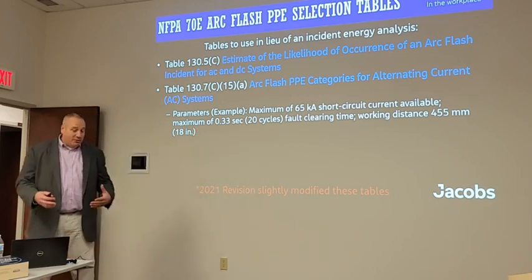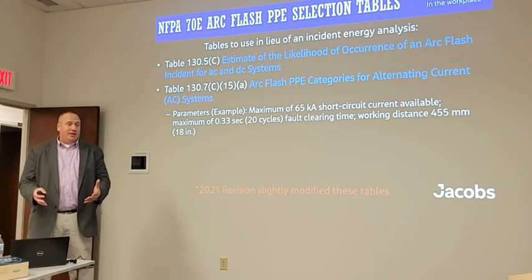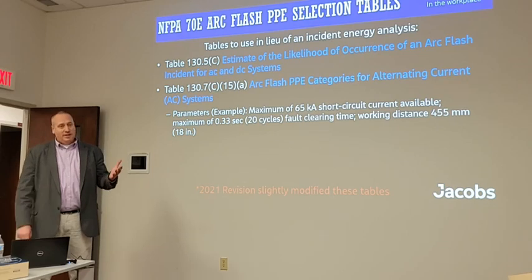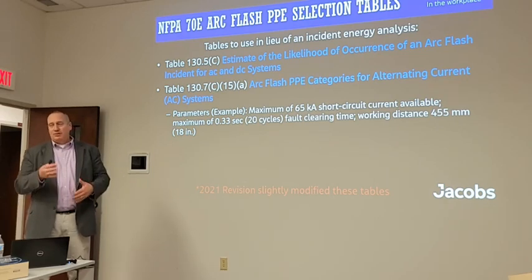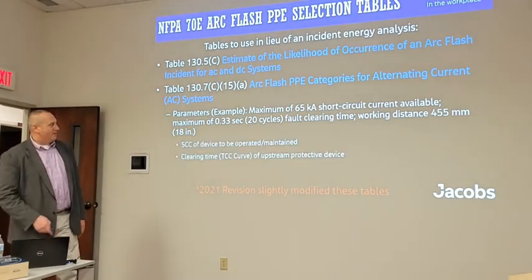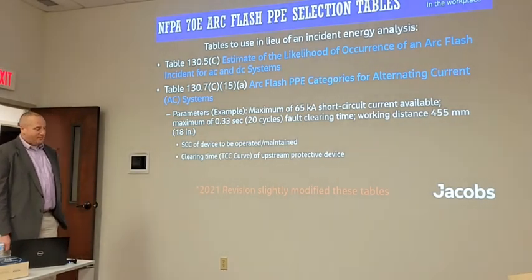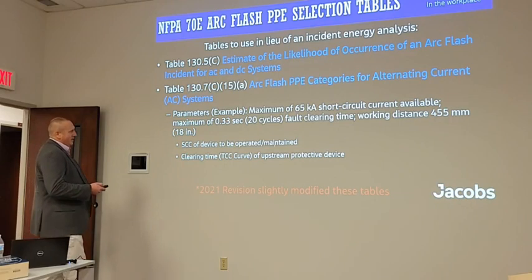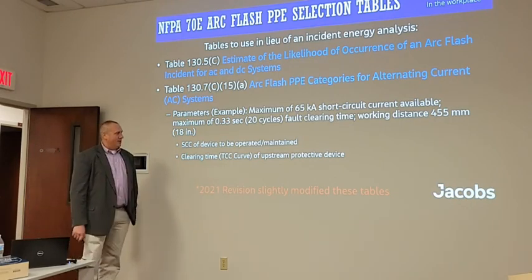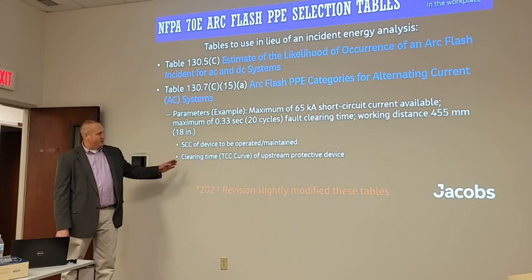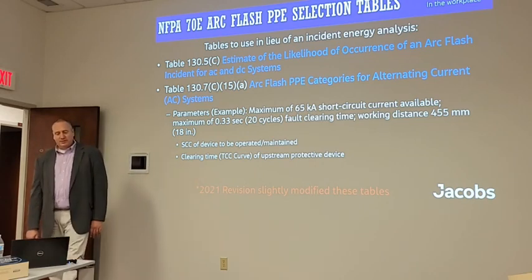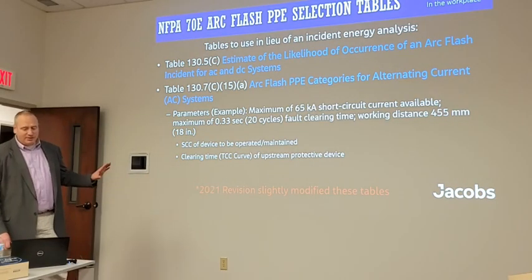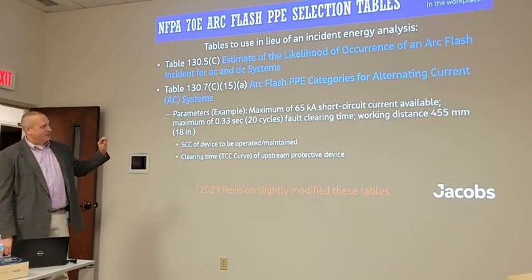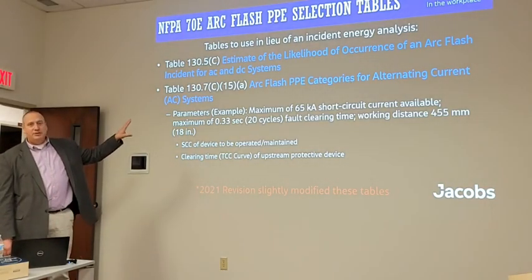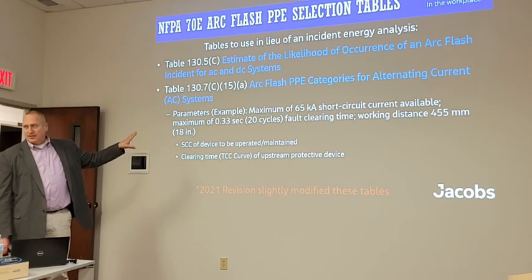Well, to do the arc flash analysis, I'm looking up make and model of a breaker or a fuse, whatever it is, and getting the time current characteristics curve and doing an evaluation based on the manufacturer's curve. And so you're not going to know the short circuit current of the device you're operating or maintaining out in the field. You're not going to know the clearing time of the upstream protective device. So I would argue that I have yet to find any scenario in the field that these tables are being used the way the 70E intends them to be used.